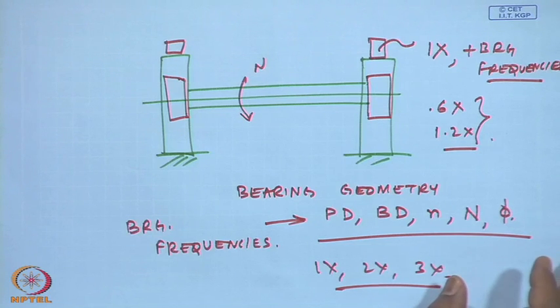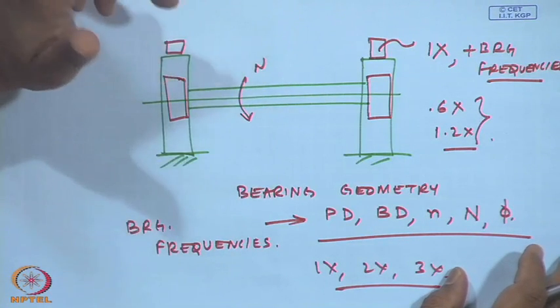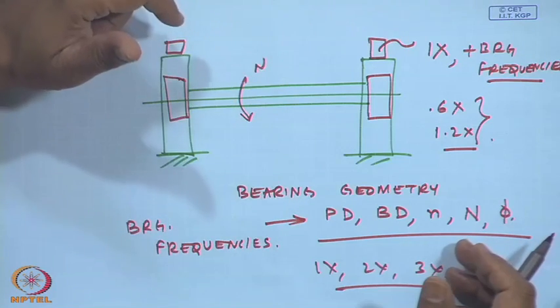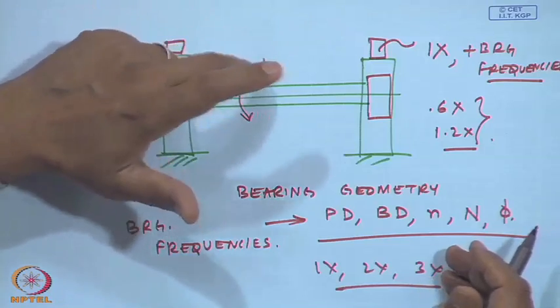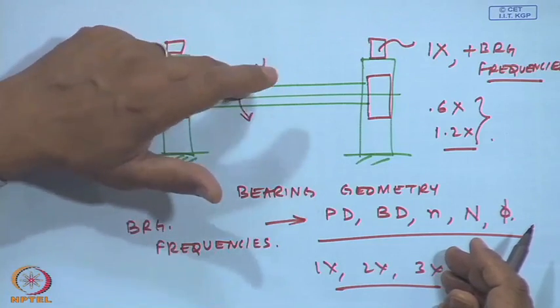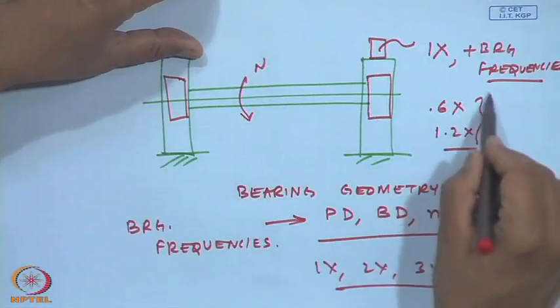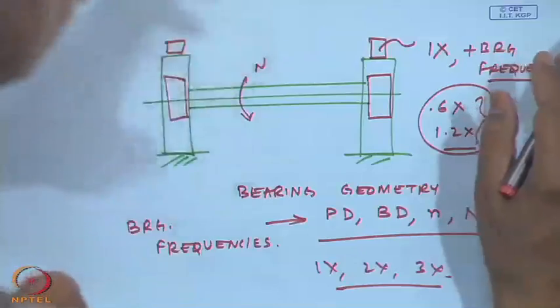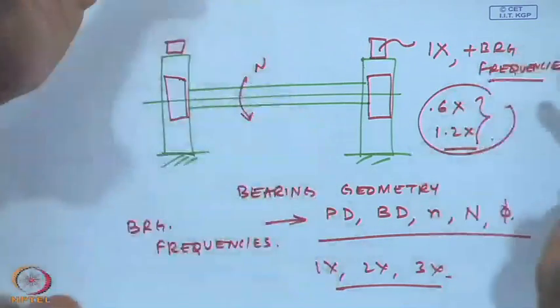And that is again why you may be wondering, well, I am always putting my transducers on the bearing mounts. What if the bearing frequencies are contaminating or mixing with my actual shaft defect frequencies of misalignment, crack, unbalance? That will not happen because they are at different frequencies. The bearing frequencies themselves are at a different value compared to the shaft frequencies, and that is actually helping us. And like I told you in spectrum analysis, every peak in the vibration spectrum corresponds to a particular defect in a particular mechanical element. It could be a bearing fault, a shaft fault, an unbalance, or a gearbox fault. They are all different frequencies, and that has really saved the work for us. Okay.